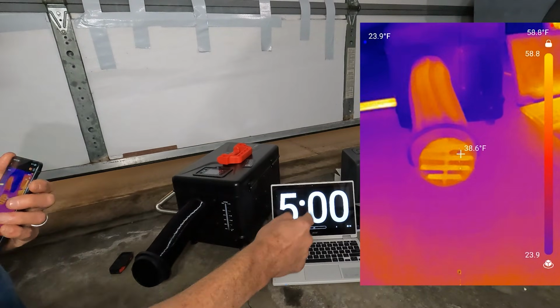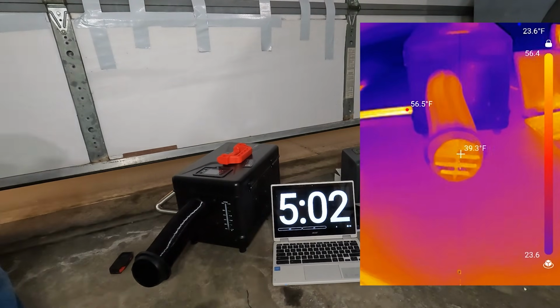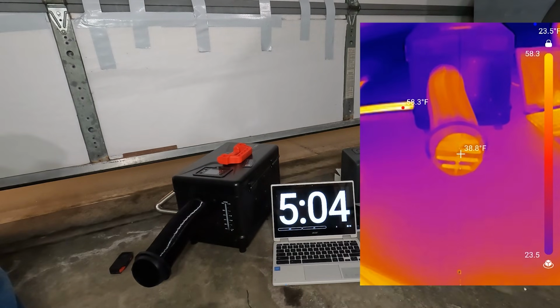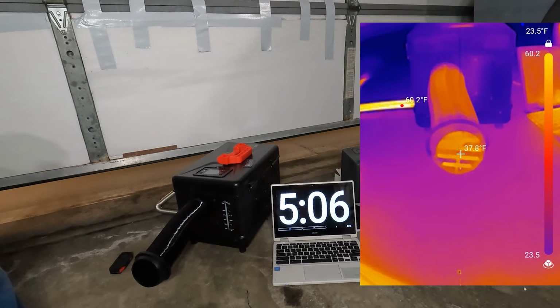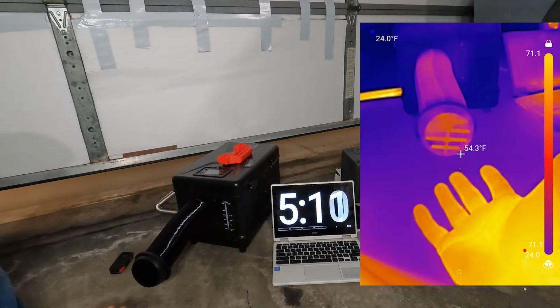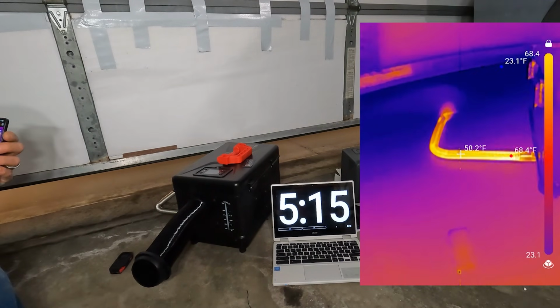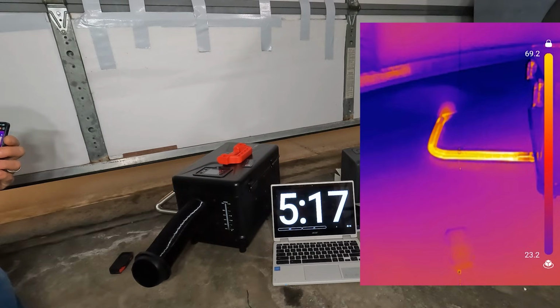Okay, we are now at 5 minutes, and as you can see on the thermal camera, we're still at 39, 38 degrees Fahrenheit. So still cold air blowing out of this unit. The exhaust pipe is getting hotter, which is good.